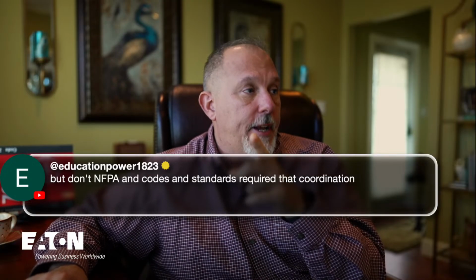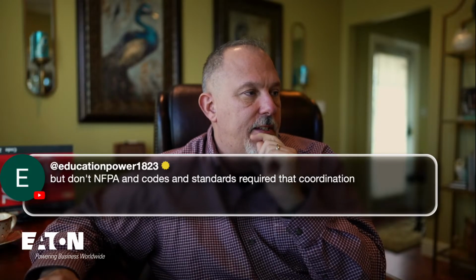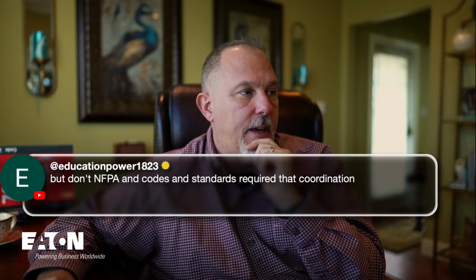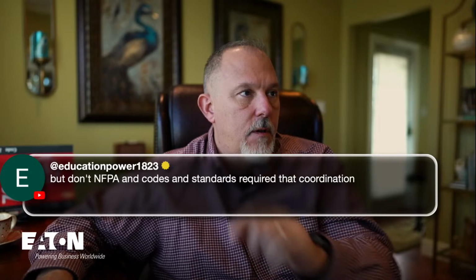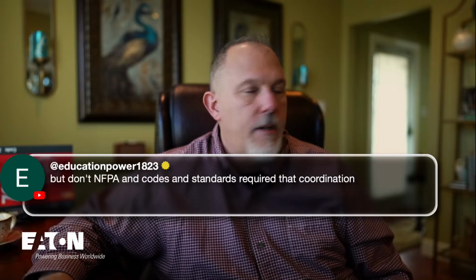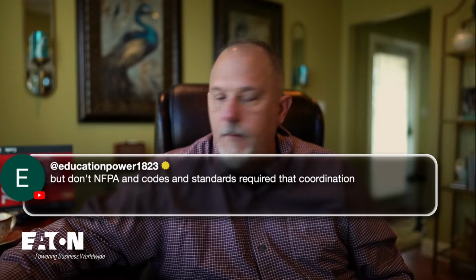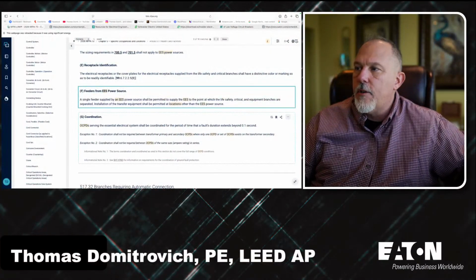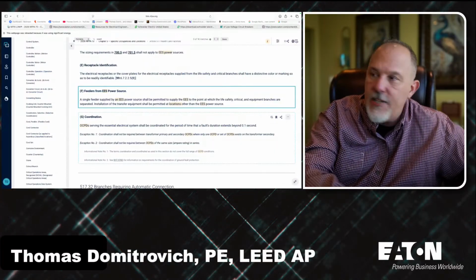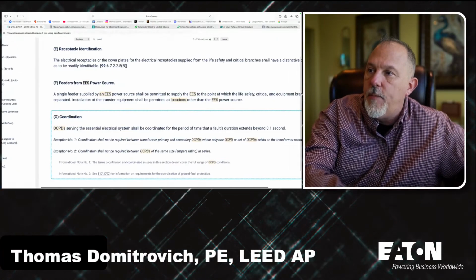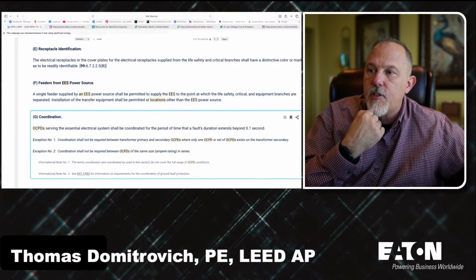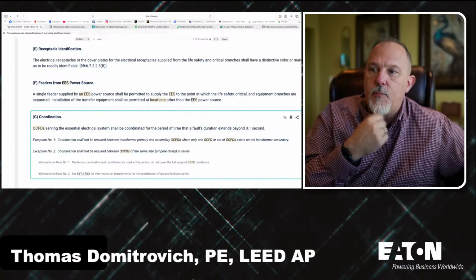In fact, let me go back to 517 on coordination. If you go to 517, what it says for healthcare, Control F, coordination. Here we go. It says overcurrent devices serving the essential electrical system shall be coordinated for the period of time that a fault's duration extends beyond 0.1 seconds.